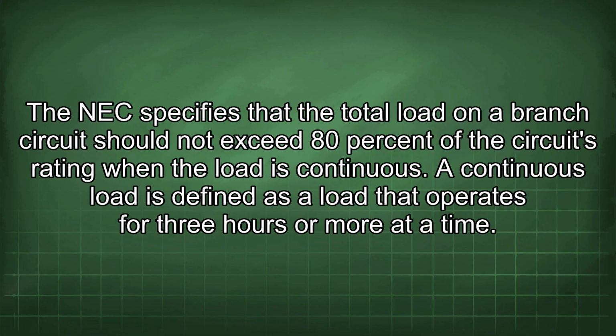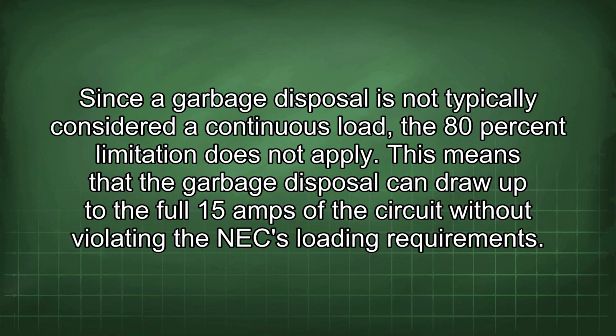To further clarify, consider the NEC guidelines on branch circuit loading. The NEC specifies that the total load on a branch circuit should not exceed 80% of the circuit's rating when the load is continuous. A continuous load is defined as a load that operates for 3 hours or more at a time. Since a garbage disposal is not typically considered a continuous load, the 80% limitation does not apply.